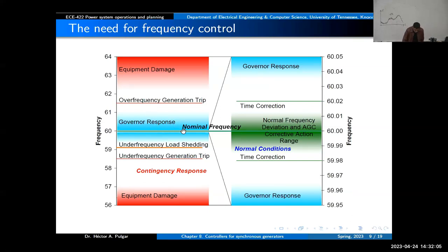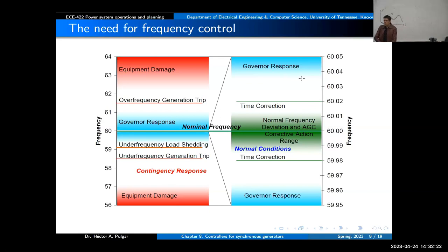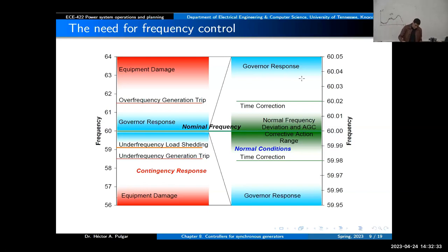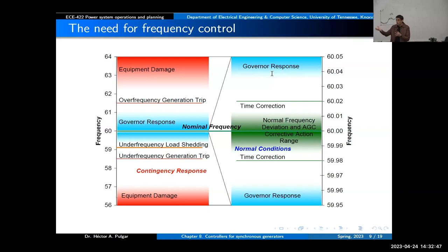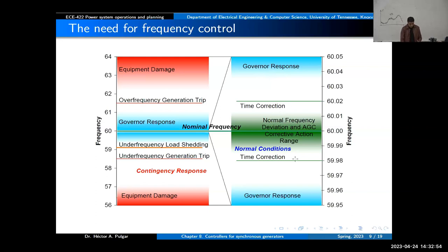Around the nominal frequency, you look at a much smaller range where other actions happen. You will have a governor response. The governor controls either the power or the frequency in the generator. Typically, we will have a dead band — if the frequency is within the dead band, there will be no action on the adjustment of power generation. And here you also have the time correction that is applied.